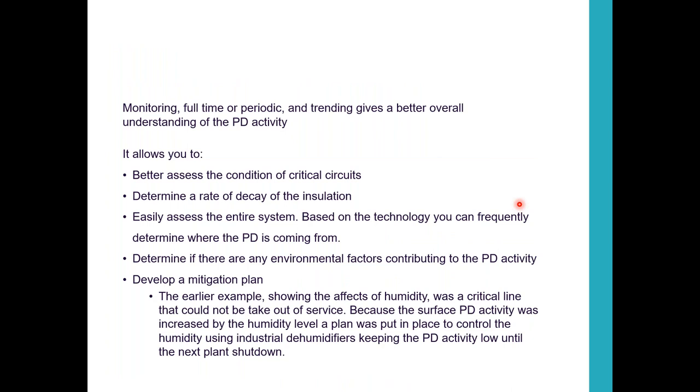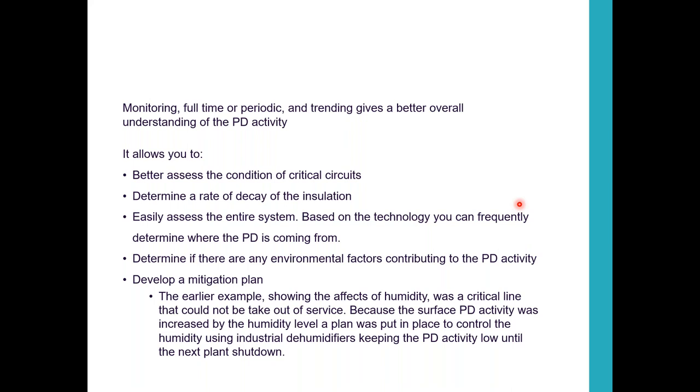It gives you full-time ability to better assess the condition on critical circuits, and at any time look at it and see if it's getting worse. Or if you're doing periodic testing, you have to send someone out to take the readings every time, whether it's monthly or every 6 months, and develop the database, develop your charts to see how it's trending. So it gives you a lot of flexibility on where you're going, what you're doing, and a lot more visibility into your system.